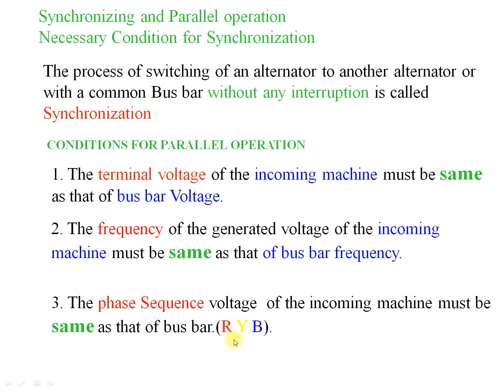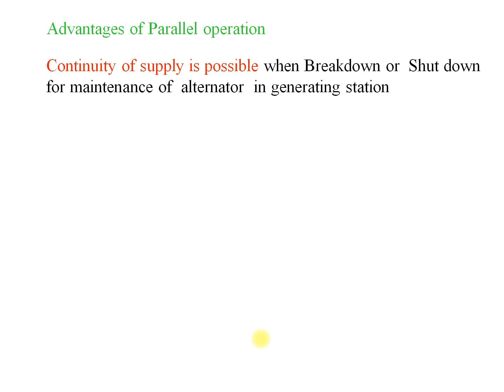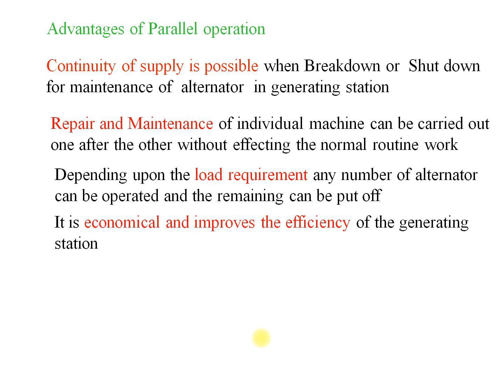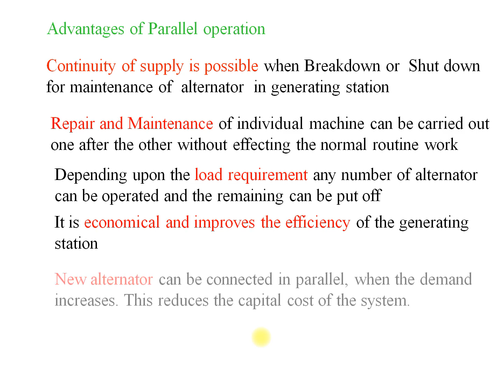The advantages of having parallel operation are that continuity of supply is possible when there is a breakdown or shutdown for maintenance of an alternator in the generating station. During repair and maintenance time, the parallel operation is very important. Also, depending upon the load requirement, any number of alternators can be operated. So for economy and improving the efficiency, we need to have the parallel operation of the machines.